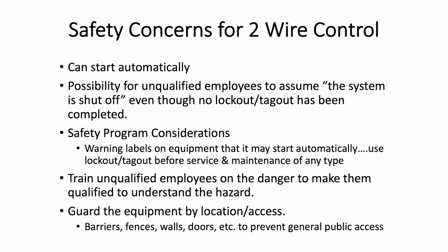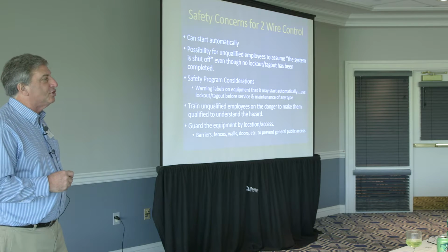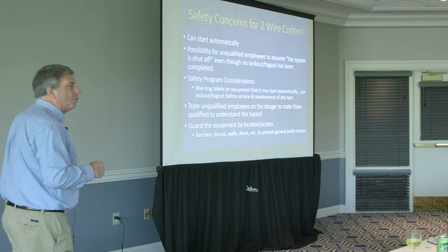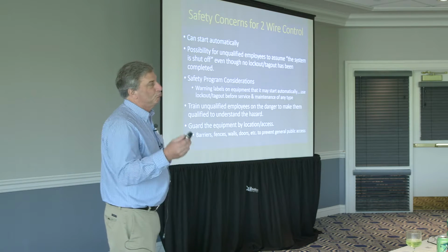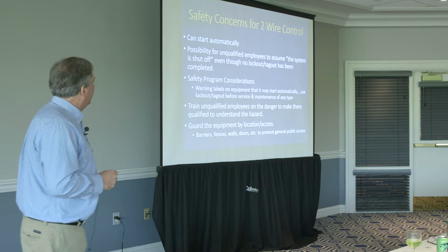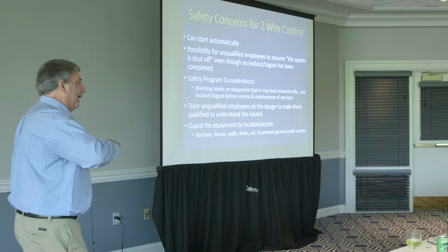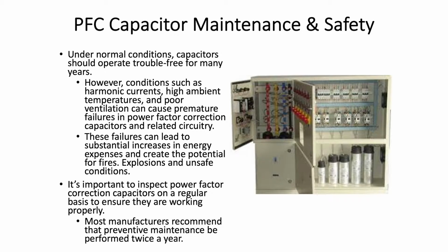Possibility for unqualified employees to assume the system's shut off even though no lockout tagout's been completed. Warning labels on equipment that might start automatically. Use lockout tagout before service and maintenance of any type. Something like that. Train unqualified employees on the danger to make them qualified to understand the hazard and guard the equipment by location or access so those unqualified folks can't get to it to screw up. Those are some options then typically that can be used to, okay, if we've got a concern for this, what can we do? Now, power factor correction, maintenance and safety.